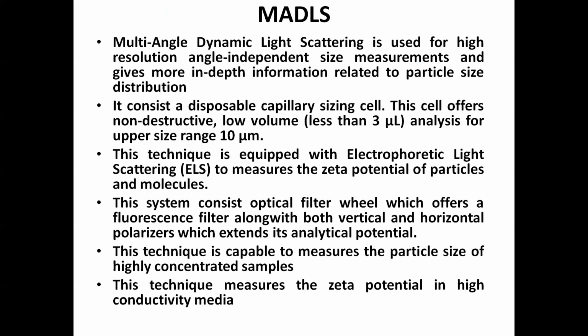The multi-angle dynamic light scattering technique is also used for high resolution angle independent size measurement. And this technique gives more in-depth information related to particle size distribution. It consists of a disposable capillary sizing cell. This cell offers non-destructive low volume, which means less than 3 microliters is sufficient for analysis. And the upper size range is 10 micron. So this will measure a maximum of up to 10 micron, which means there is a minimum that is permissible, but the maximum is 10 micron.